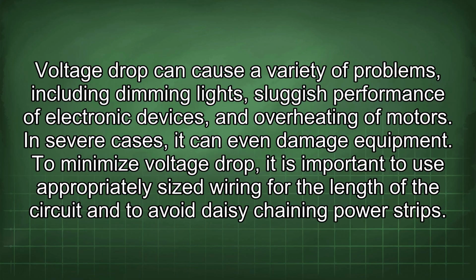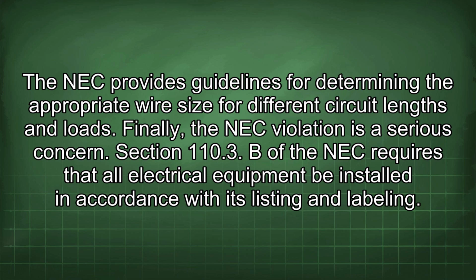To minimize voltage drop, it is important to use appropriately sized wiring for the length of the circuit and to avoid daisy-chaining power strips. The NEC provides guidelines for determining the appropriate wire size for different circuit lengths and loads. Finally, the NEC violation is a serious concern.